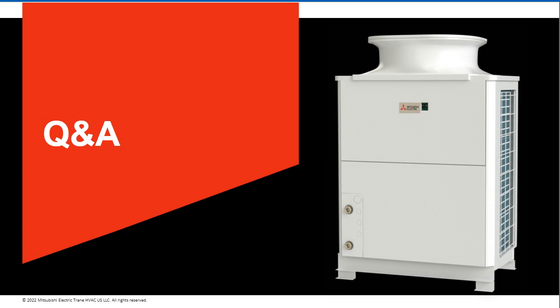No, the CO2 in the heat pump itself is a closed system, so if you lose power, it's just going to turn the compressor and fan off and sit idle until power's reapplied, and then it would go through its initiation startup process again and run without a hitch from there. And the biggest concern would be if you lost power in a cold climate and you froze some pipes, like if you weren't circulating because the heat trace was off, or the pump inside the heat pump water heater couldn't circulate water. That would be the biggest concern.